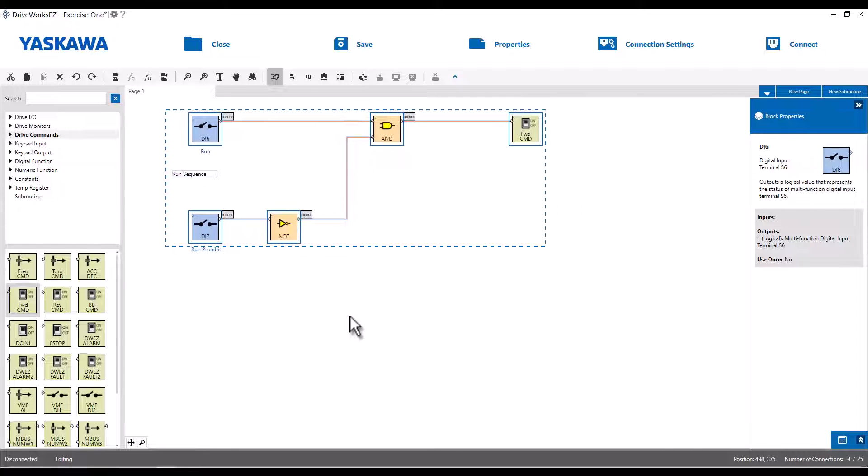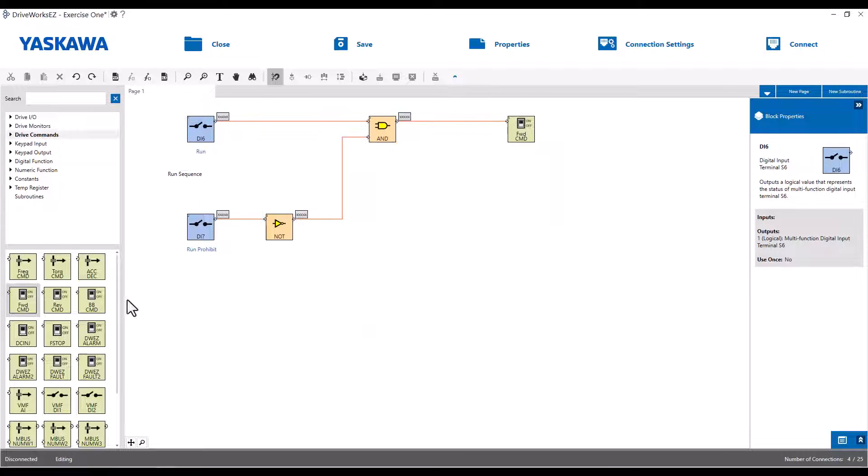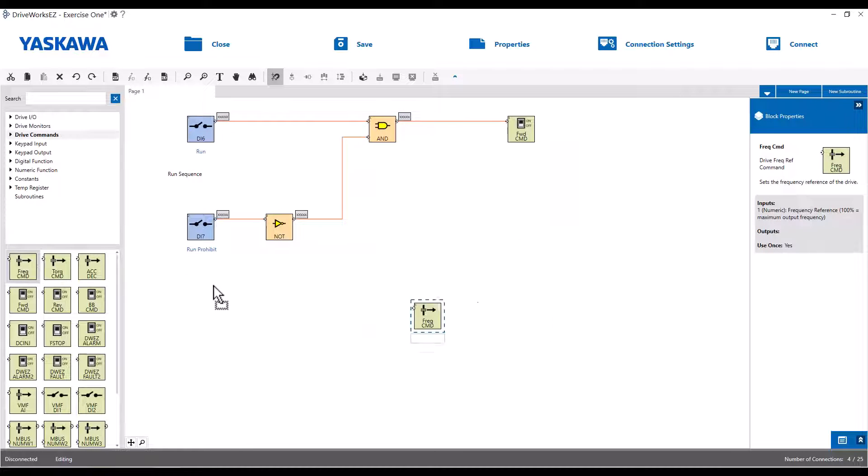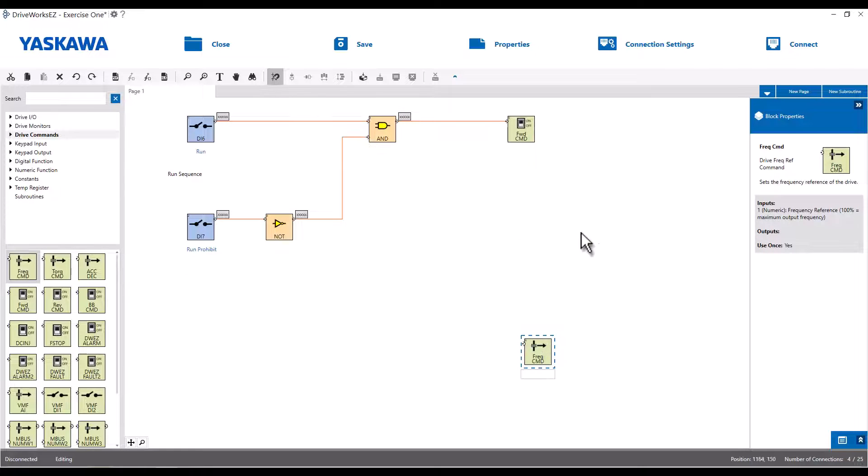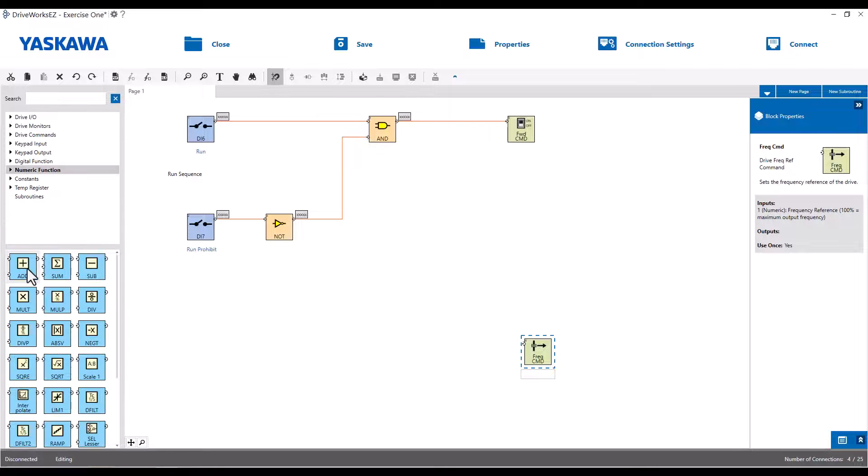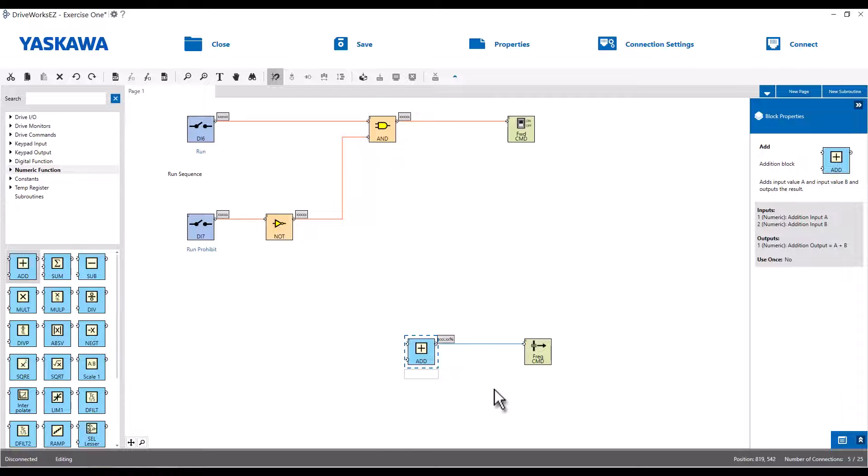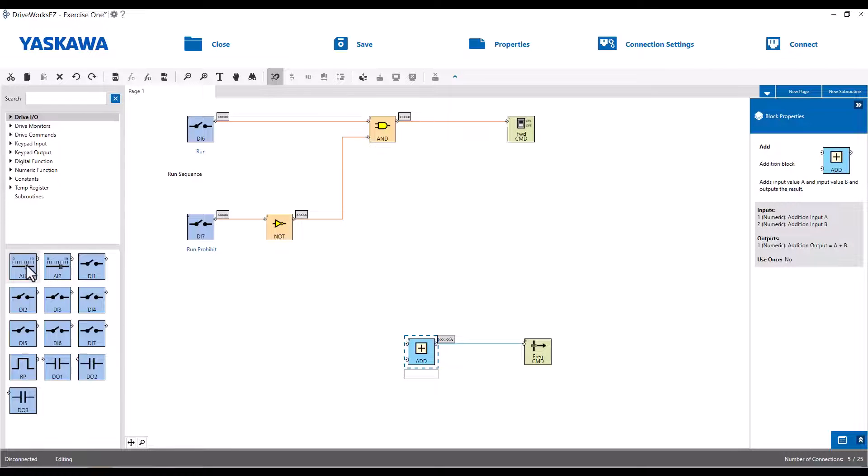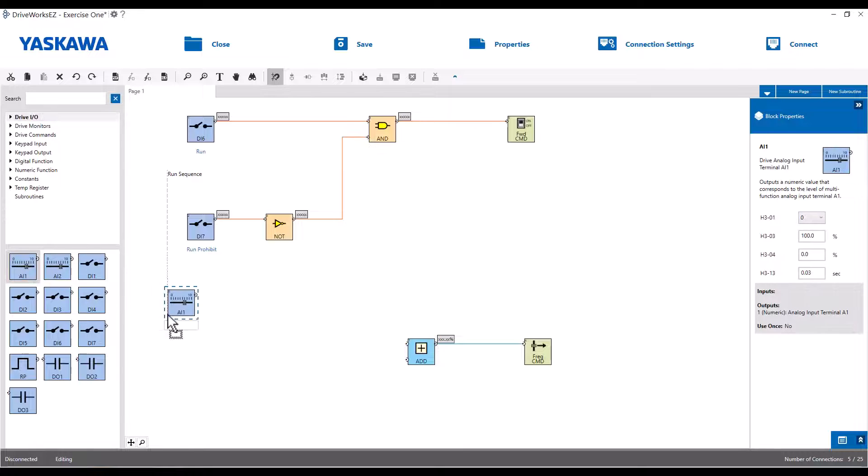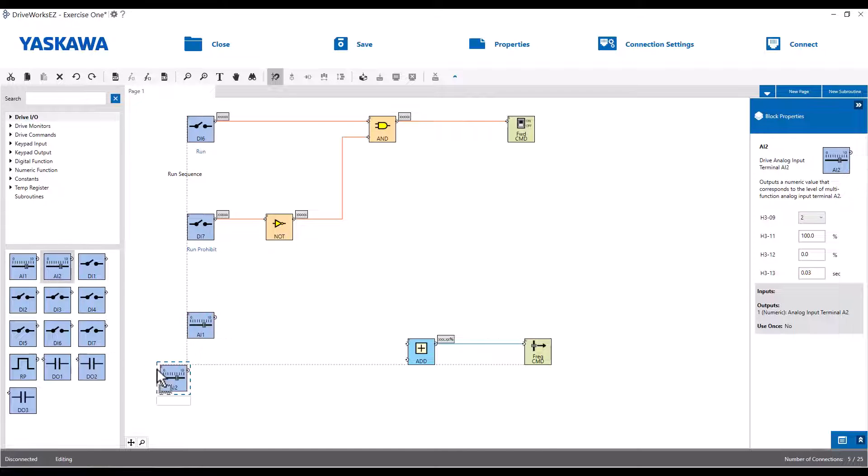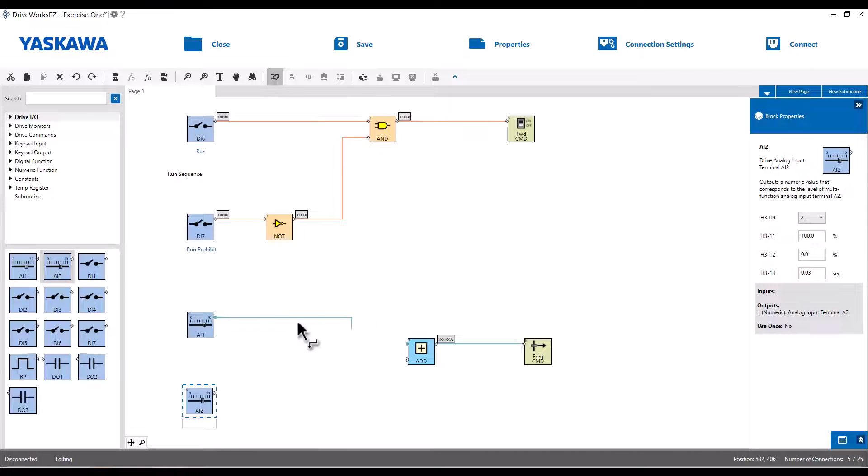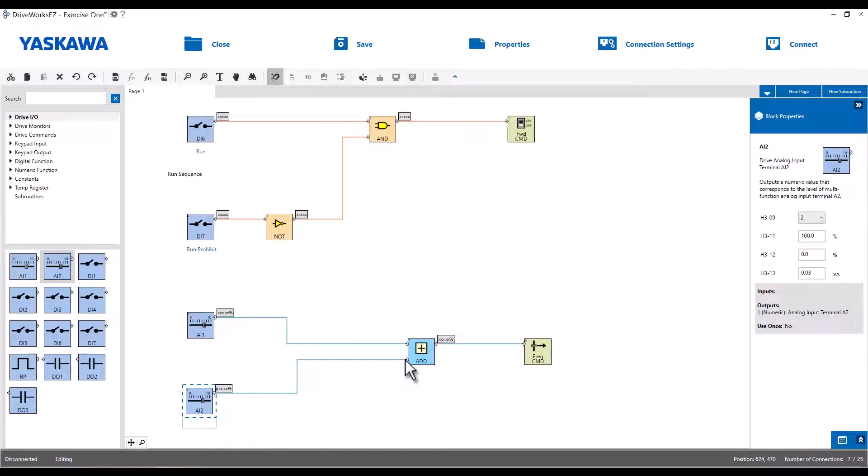So I'll need a frequency command, and that actually will be the output telling the drive how fast to run. We're going to add our analog inputs together. So for that, you can take a wild guess, and yeah, we're going to use an add block. So under the numeric function, there's an add block I will drag out onto here. I'm kind of building this backwards by starting from the output. Go to the drive IO. We said we wanted AI1 and AI2. Make these connections here. You can highlight the stuff and arrange them vertically and horizontally to make them look nice. And just for continuity, I'm going to add text to this to say this is our frequency reference.